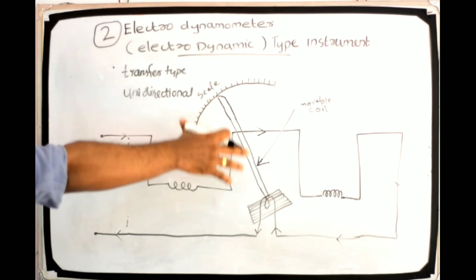Next is the electrodynamometer wattmeter. The two coils are connected in different circuits for measurement of power. The fixed coil or field coils are connected in series with the load and so carry the current in the circuit. The moving coil is connected across the voltage and therefore carries a current proportional to voltage.